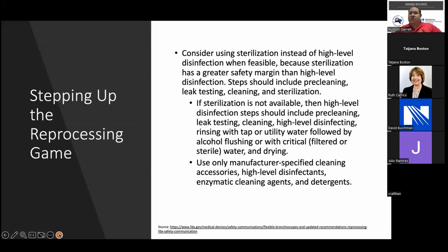We may have to take incremental approaches, within the lines of the manufacturer's validation, to increase the likelihood of success. So maybe you were only doing low-level disinfection and didn't realize you were supposed to be doing high level. Well, get up to at least the minimum level now. Or if you're doing high level and want to go to sterilization, that's something you can be proud of because we're always moving that needle forward to advance patient safety with some of these quite risky devices.